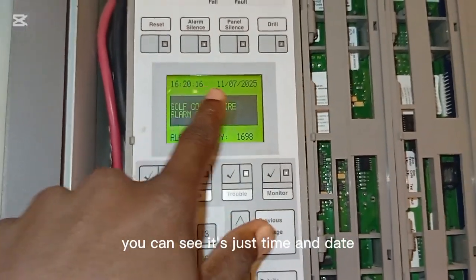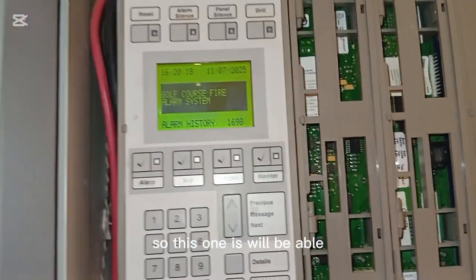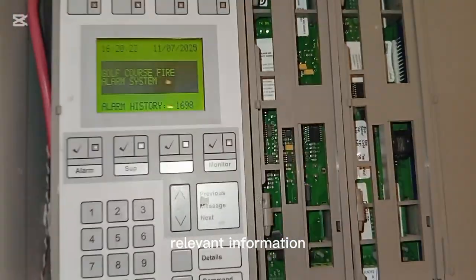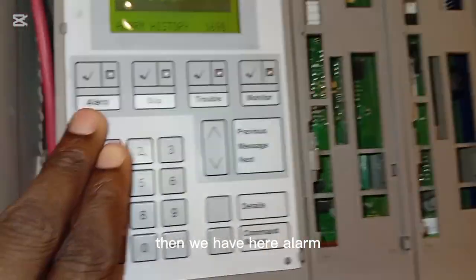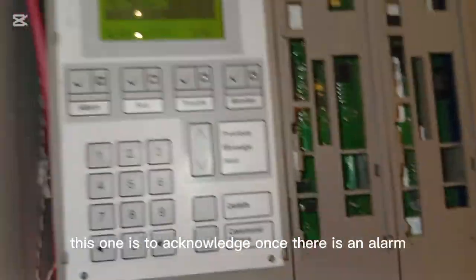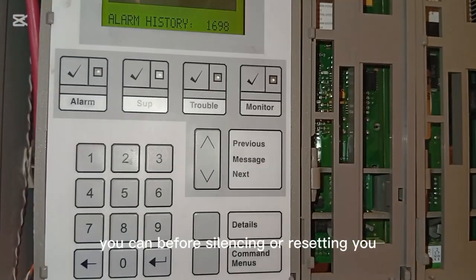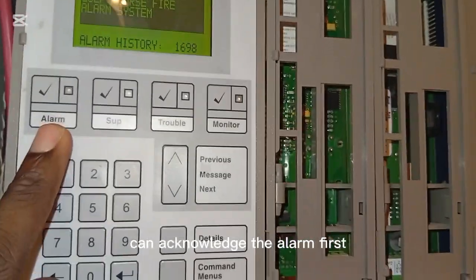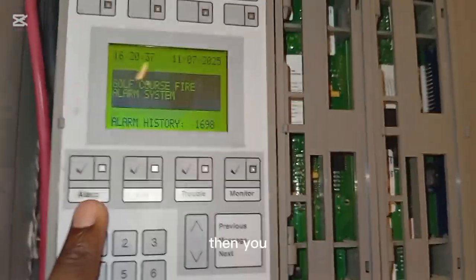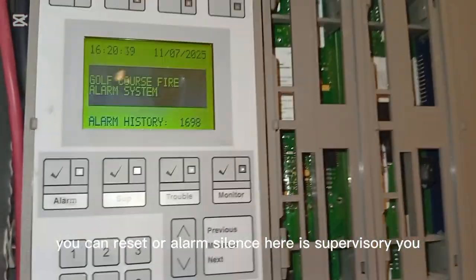You can see just the time and date. So in the case of an alarm, this will be able to provide you with relevant information: the date and the time the alarm occurred. Then we have the alarm button. This one is to acknowledge. Once there is an alarm, before silencing or resetting, you can acknowledge the alarm first, then you can reset or silence the alarm.